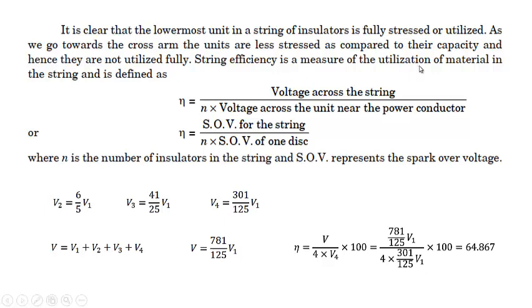So string efficiency is a measure of utilization of material in the string and is defined as follows. String efficiency will give us an idea of the utilization of the insulators. If string efficiency is less than 100%, it means the utilization is not proper. We are not utilizing it fully. If string efficiency is equal to 100%, which is not practically possible, that means there is uniform distribution of the voltage. All the disks have the same voltage. So it is given by the total voltage across the string, divided by N, the number of insulators in the string, times the voltage across the unit nearest the power conductor.